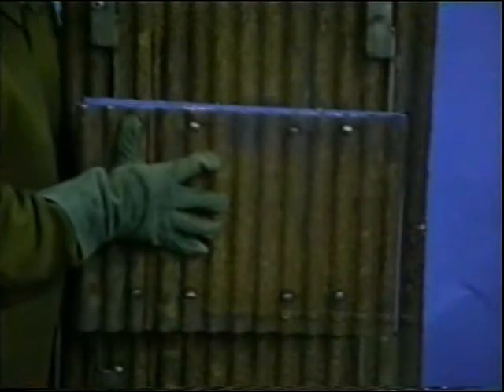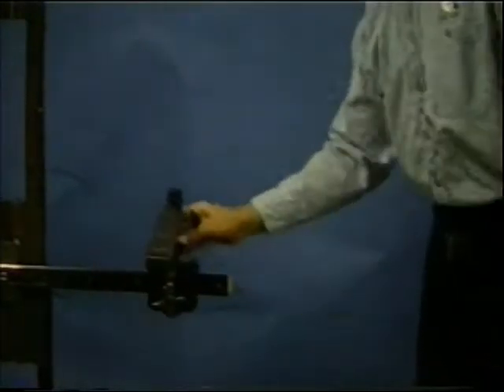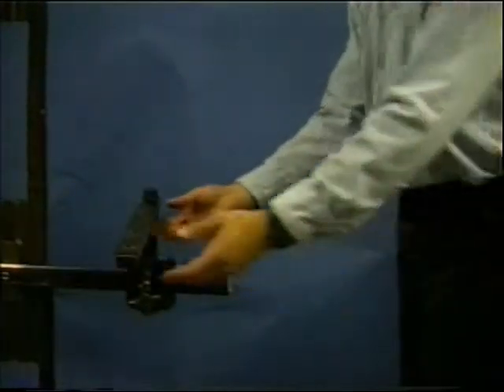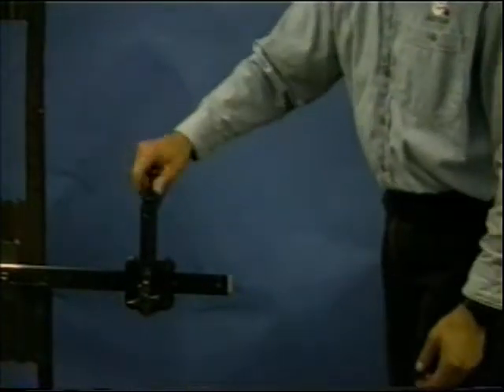When the second vertical cut is complete, the panel is removed and the track is remounted to the lower weld tabs for membrane removal. Once the track has been mounted, the membrane bracket is slid onto the track. As you can see, the membrane bracket can be rotated to different positions.